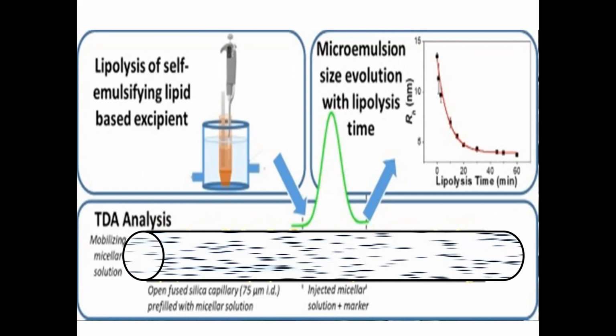So this is the view. This is a tube. Inside that tube, your particles are suspended in a liquid. There is a laser source that will be incident on the cross-section of this tube, and whatever particles come in front of it, this laser light will track the position as well as the size of those particles. The image will be captured on the opposite side of this tube, and then image processing will take place, and ultimately you will get the size distribution and all these things.